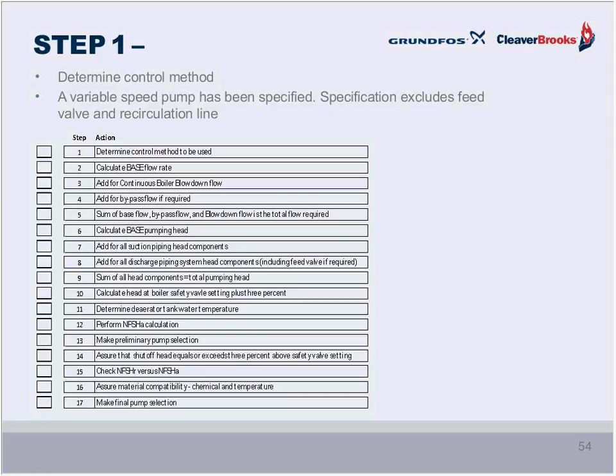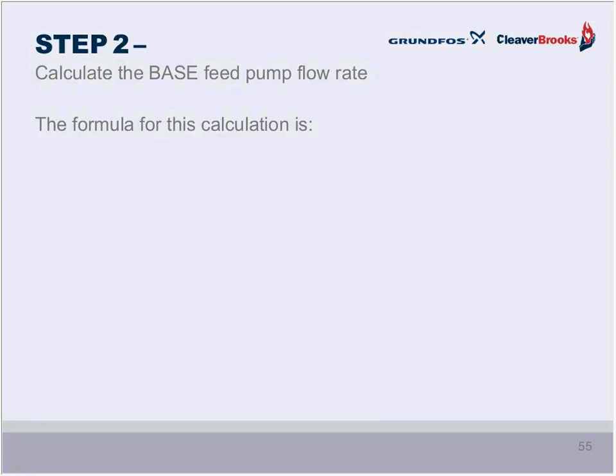So as we did last time, we use this process to check off each of the steps as we go. I'll probably check off about every fifth one in the interest of time here. So the first one is to determine what control method we're going to use. Well, we're going to use a variable speed pump with no feed valve and no recirc line. We picked that up from the specification.